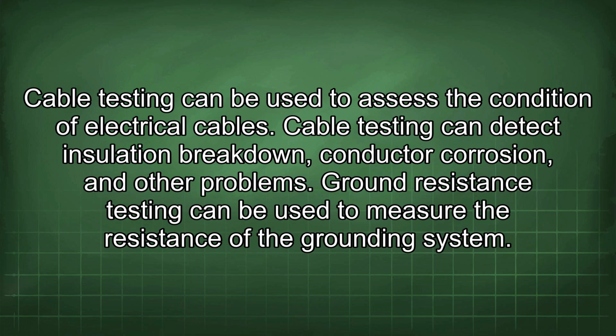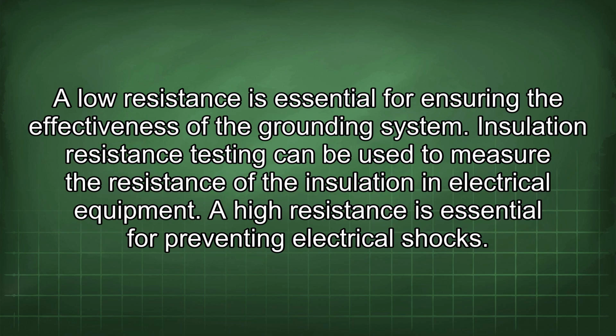Ground resistance testing can be used to measure the resistance of the grounding system. A low resistance is essential for ensuring the effectiveness of the grounding system. Insulation resistance testing can be used to measure the resistance of the insulation in electrical equipment. A high resistance is essential for preventing electrical shocks.